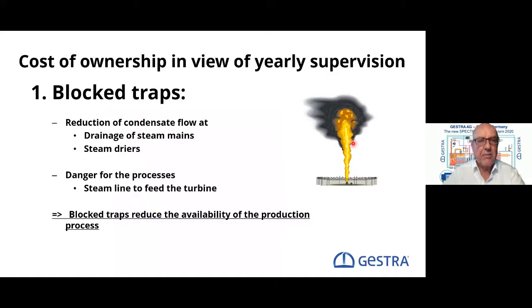In the second part of this presentation, I would like to speak about the cost of maintenance. Does it make sense to change the steam traps, or would it be a good idea to change the internals every 5 years? And shall a customer make a supervision every 6 months, every year, or only every three years? Blocked traps are normally indicated very quickly, because the product will not be heated in a sufficient way. That is not a problem. To avoid problems, it is recommended to clean the strainer of a thermostatic trap once every year.